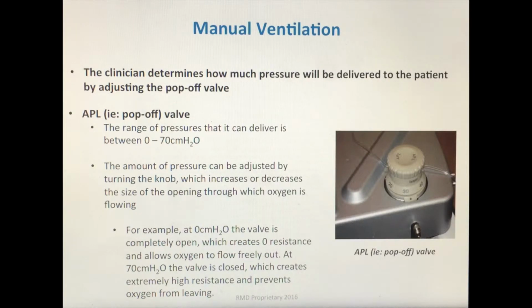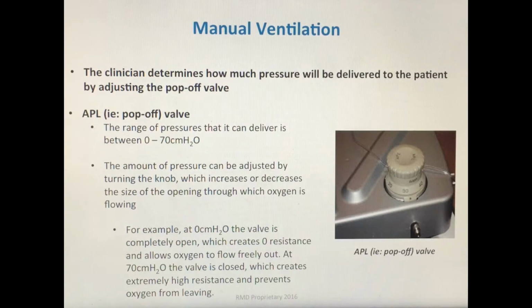Typically, the pressure to set for nasal CPAP is between 10 and 20 centimeters of water pressure. The pressure for nasal ventilation should be set between 20 and 30 centimeters of water pressure. As you can see in this picture, the pop-off valve is set at 30 centimeters of water pressure, which means that there will be 30 centimeters of water pressure built up within the patient's nasopharynx and the patient's lungs, assuming there are no leaks in the system.